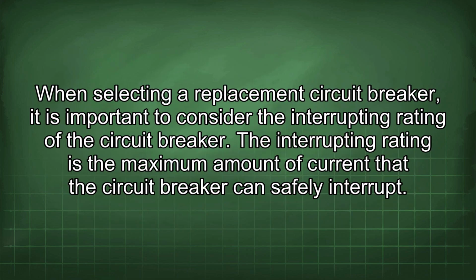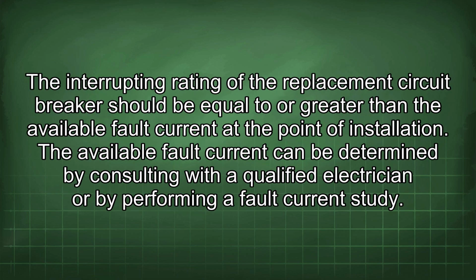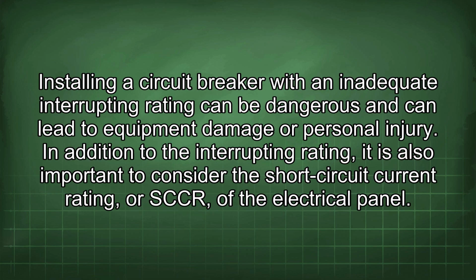When selecting a replacement circuit breaker, it is important to consider the interrupting rating of the circuit breaker. The interrupting rating is the maximum amount of current that the circuit breaker can safely interrupt. The interrupting rating of the replacement circuit breaker should be equal to or greater than the available fault current at the point of installation. The available fault current can be determined by consulting with a qualified electrician or by performing a fault current study. Installing a circuit breaker with an inadequate interrupting rating can be dangerous and can lead to equipment damage or personal injury.